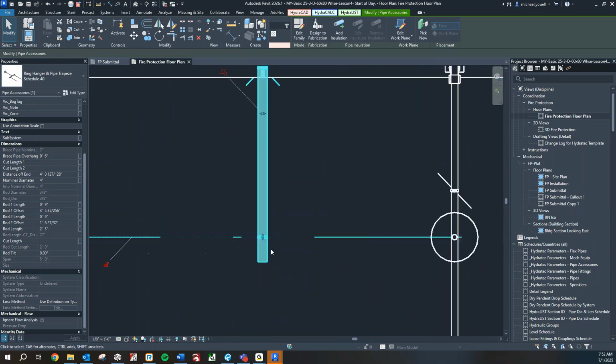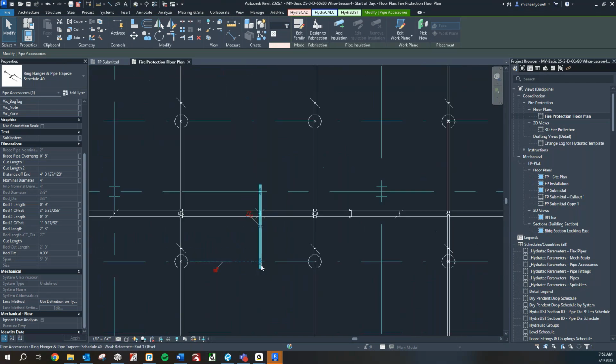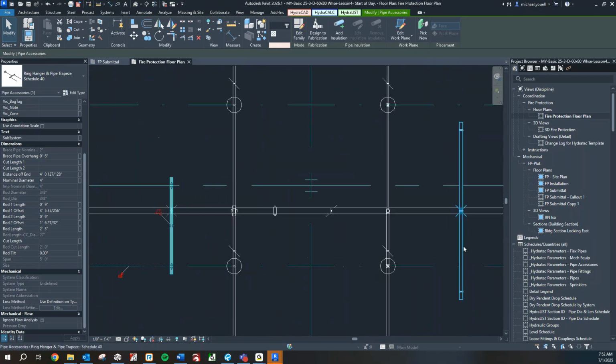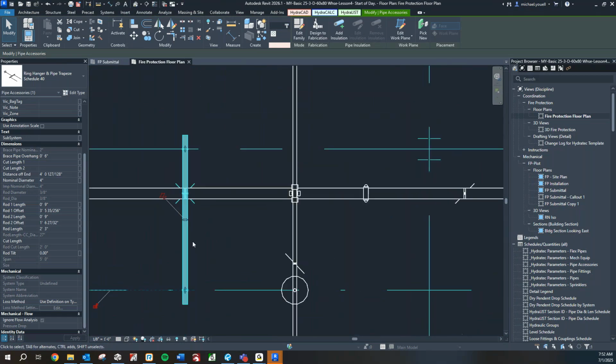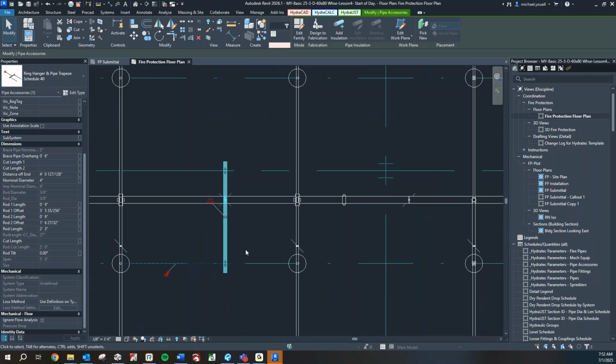You have to squint a little bit, but that pipe is a lot thinner than it was when it was long. Oh wow. So it's doing the calculation for we're holding up a 4-inch pipe over this span. So when you make the span smaller, the pipe gets smaller. Oh, like it'll actually change the pipe size automatically for you for the hanger. Yes, for the trapeze bar. Yes.